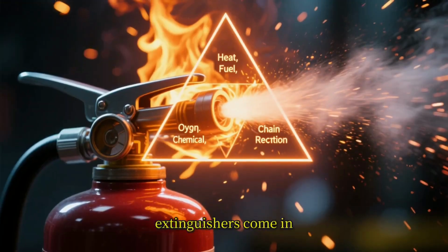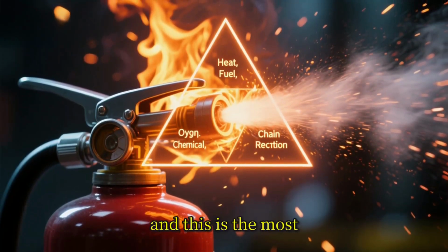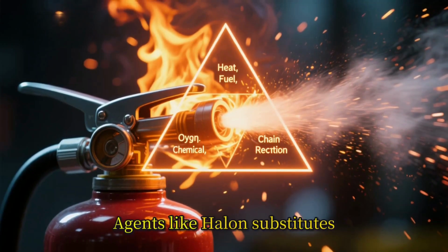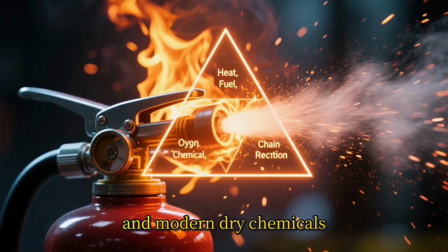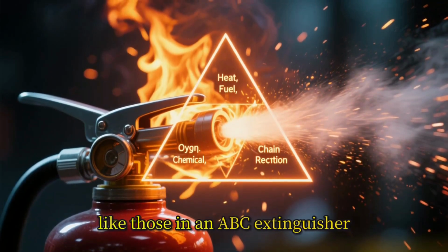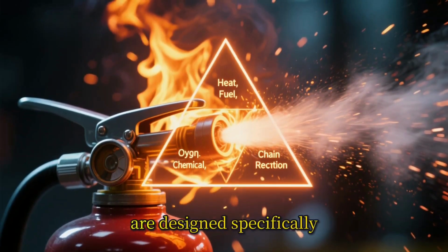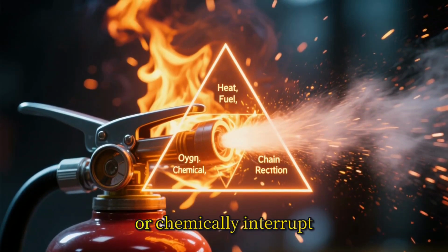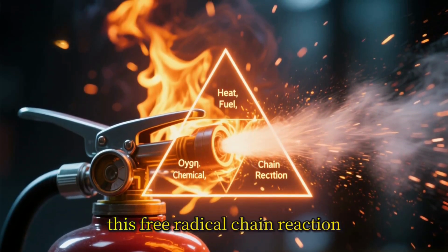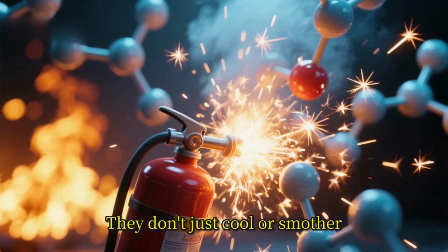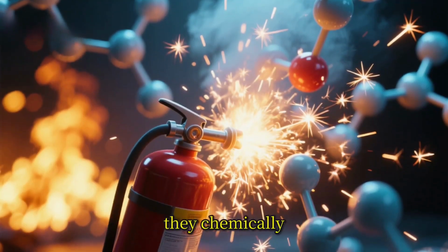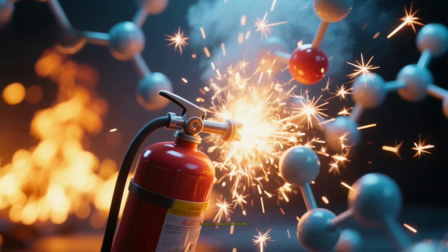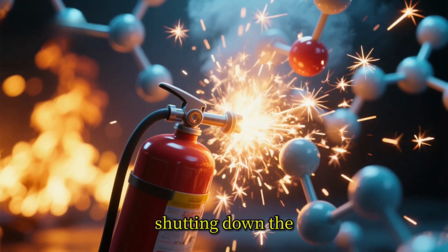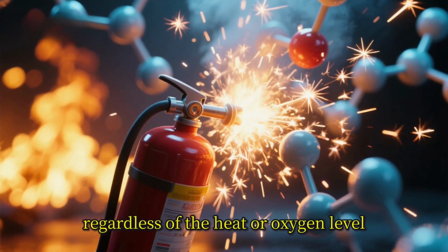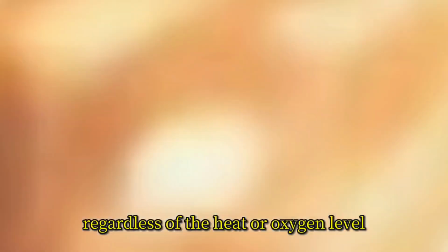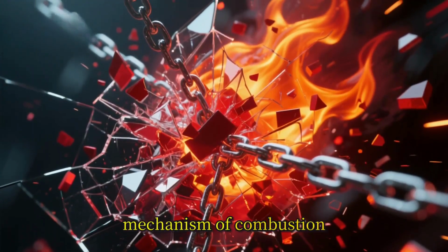This is where advanced extinguishers come in, and this is the most critical learning point. Agents like halon substitutes and modern dry chemicals, like those in an ABC extinguisher, are designed specifically to inhibit or chemically interrupt this free radical chain reaction. They don't just cool or smother, they chemically bind to the free radicals, neutralizing them and instantly shutting down the propagation of the fire regardless of the heat or oxygen level. They break the entire mechanism of combustion.